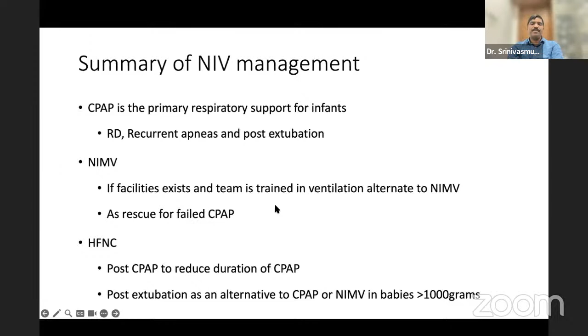And on average, you can see in your unit, if your failure rate is more than 15%, there is always a chance for us to improve on the delivery of CPAP in our babies. You need to work on improving the appropriate interface. So all three are good, but what you use, you continue to use to develop expertise in this. And prefer to use bubble CPAP machine because it's easy, cost effective. But whenever you have to use bubble CPAP, you have to ensure that you need a compressed air source, compressed oxygen source, and a good blender, and a good humidifier which delivers air oxygen at 37 with 100% relative humidity. Don't compromise on any one of this if you want good efficacy of CPAP.